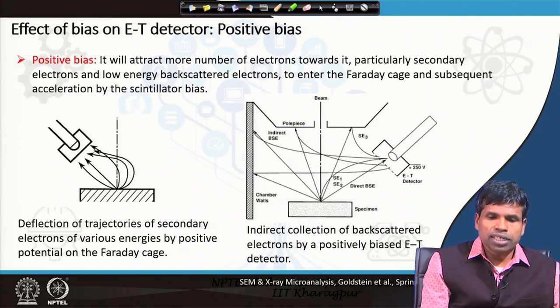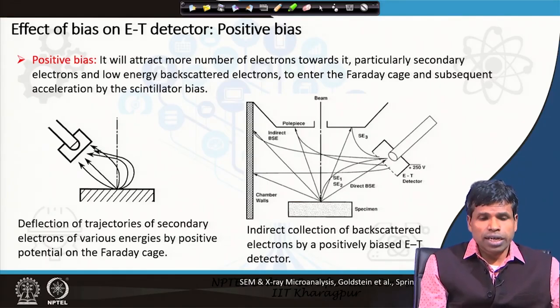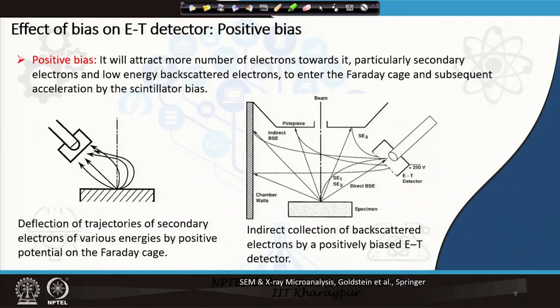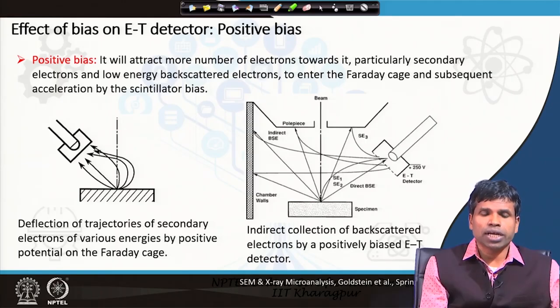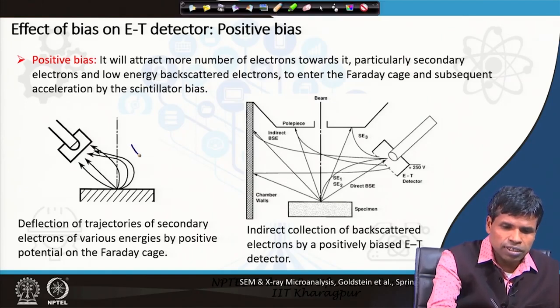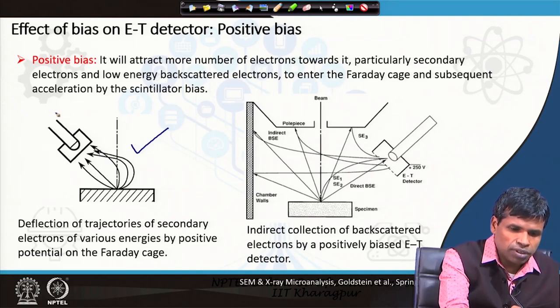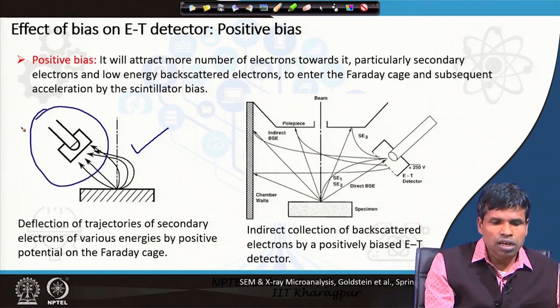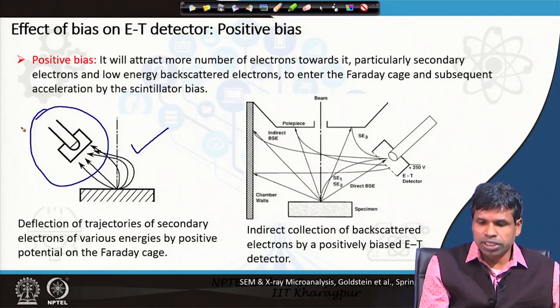Then positive bias. Positive bias certainly will attract more electrons towards the detector, particularly the secondary electrons, because secondary electrons have low energy. In addition, it will also attract low energy backscattered electrons, which would enter through the Faraday cage and subsequently be accelerated by the bias given to the scintillator. Thus, we are able to collect a large number of secondary electrons and low energy backscattered electrons by applying the positive bias. As you see, the trajectories of the secondary electrons are given here, and the ET detector is placed at an angle of around 30 to 45 degrees from the specimen.